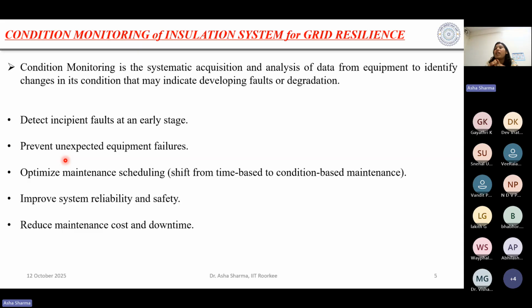Means again and again I have to monitor the condition of my insulating system so that there should not be the occurrence of any failure of the insulation. So how can I define this condition monitoring? It is a little bit of a standard definition. It is defined as the systematic acquisition and analysis of data from equipment to identify changes in its condition. What was the condition before the fault, or let's say before some disturbances, and what is the condition after the disturbance? That may indicate developing faults or degradation. Means we are trying to see the condition of the insulating material within the power system, so that if it is not attended well, it may cause some degradation or the development of a fault. So I have to take care of this insulating material.